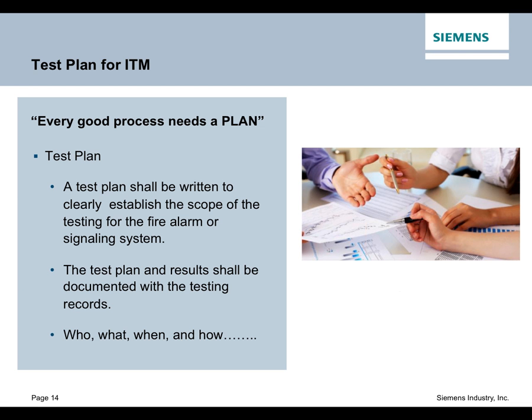That really means the fact that in today's systems, if you're sitting there in a high-rise building, you may have smoke detection that's required to be tested once a year. But for economics and logic, you may say, you know what, we're going to do 25% every quarter, so that at the end of the year, we've tested the entire system per the code. Therefore, you need to really document what floors, what zones, what number of detectors are we testing in the first test sequence, the second test sequence, the third test sequence, and what audible devices were tested accordingly.